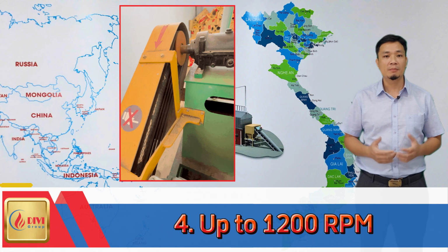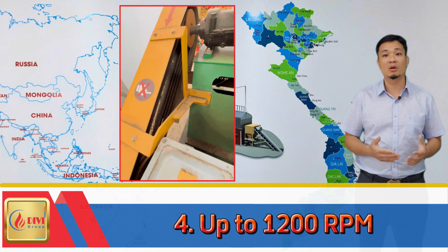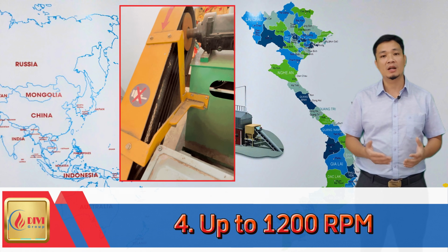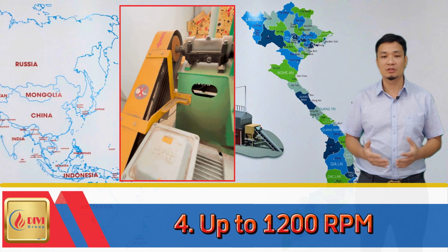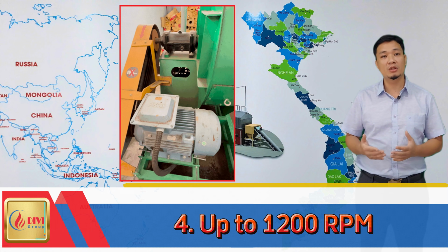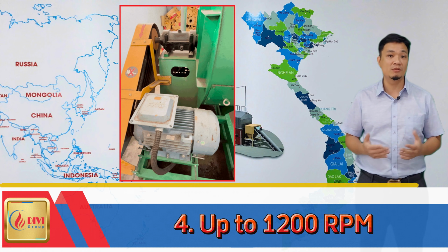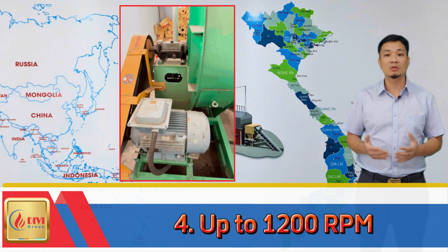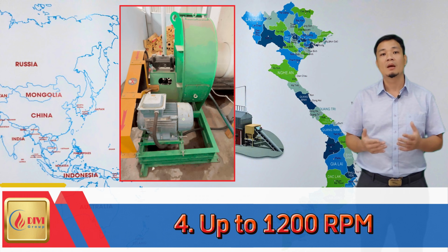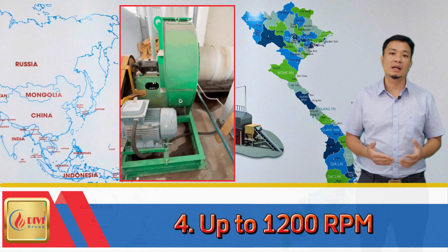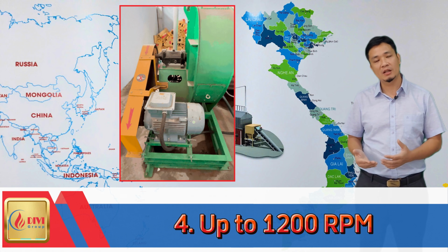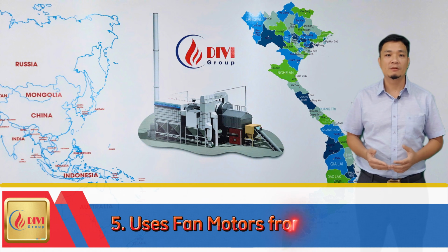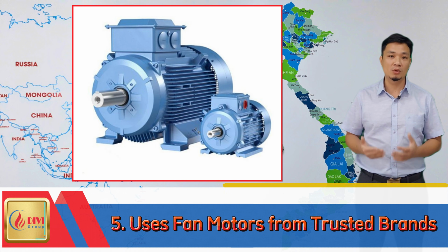4. Limit the maximum fan speed to 1,100 RPM. This reduces the velocity of flue gas passing through the blades, minimizing erosion and vibration, and prolonging the lifespan of components. We previously used low-cost, high-speed fans, but realized that reducing the speed, even at a higher cost, nearly eliminates blade wear. 5. Use fan motors from reputable brands.